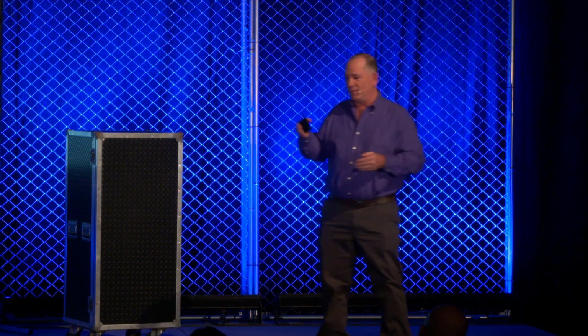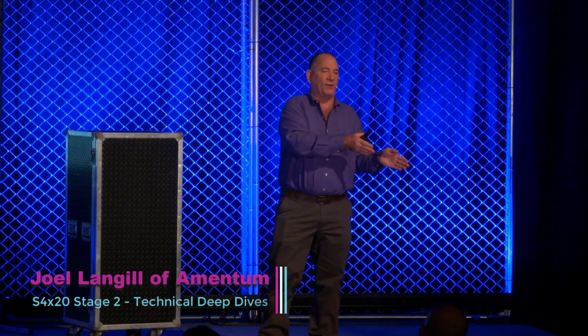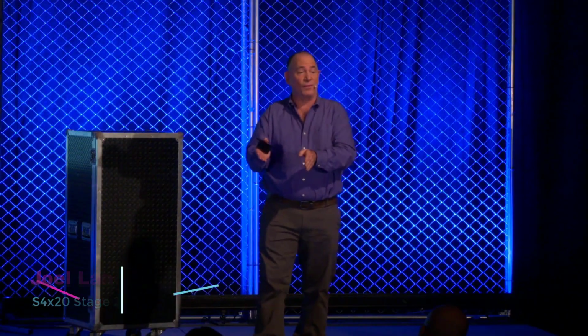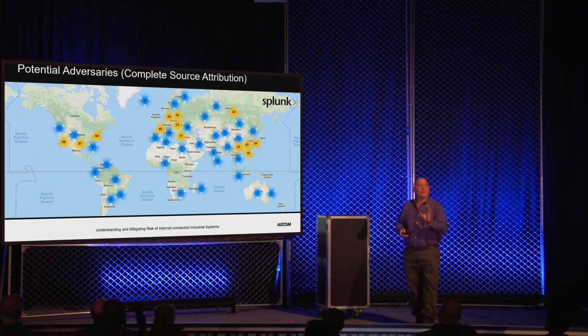So everything that hits the public IP is going to get routed to the device that would match the port translation that would occur. So if it was an 80 or a 443, it might go to the panel. But what's really scary, if you start to move it to something like Ethernet IP on 44818, it turns around and it'll go to the PLC. So this is the map.